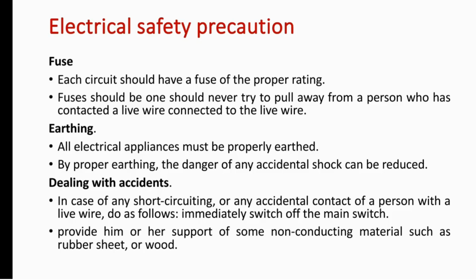Regarding fuses, each circuit should have a fuse with the proper rating — this is very important. If you are dealing with a 15 ampere load, the corresponding fuse rating at 125% is normally accepted, so almost 20 amperes. If you don't select the proper fuse rating, the fuse will not blow during overloading or short circuiting, which will create a problem for the equipment as well as the person working in that environment.